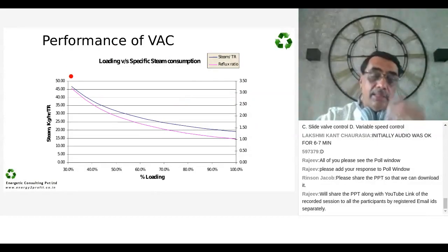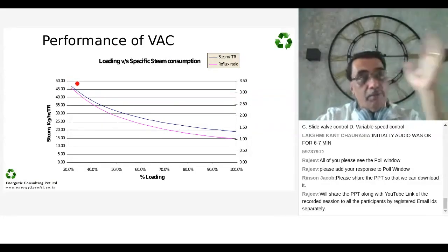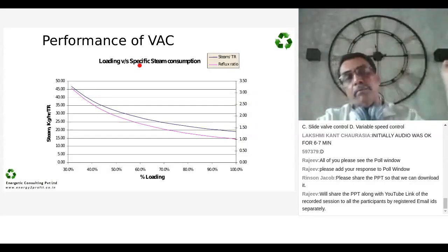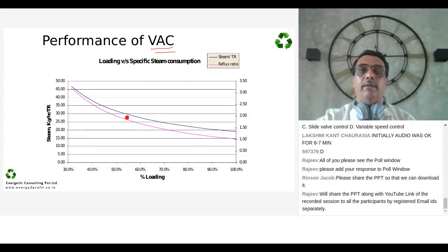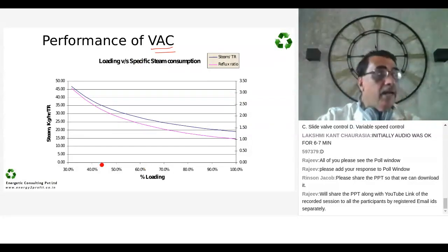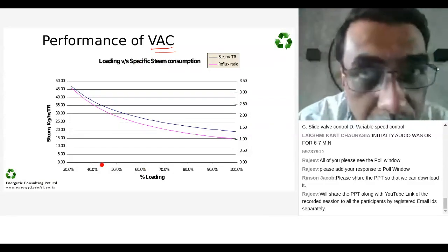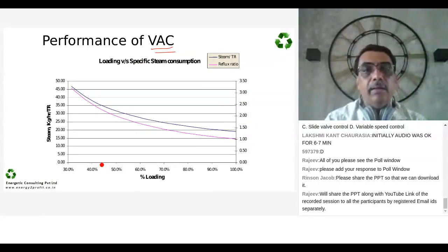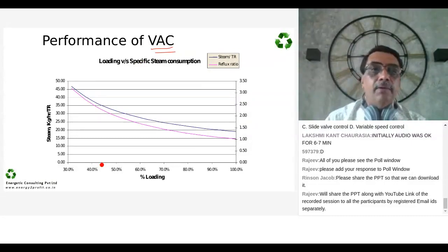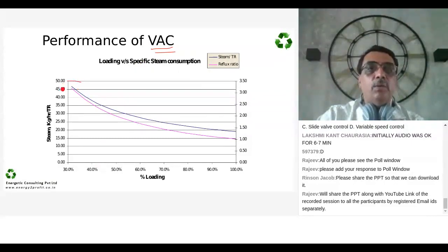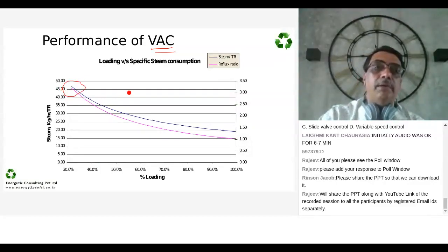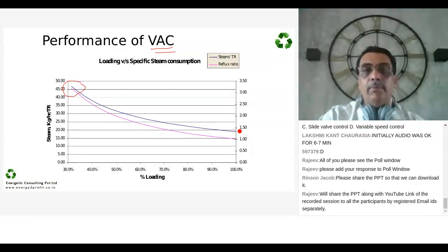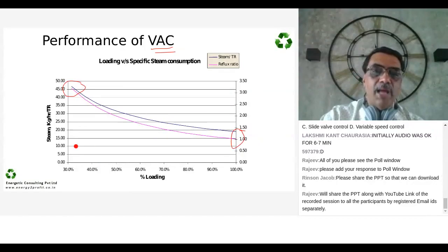This is like we saw part load performance of a vapor compression system. For vapor absorption, you have a similar one. This was again a trial done by us on a live system, with minus 20 degree brine and steam as the medium. So the steam consumption goes as high as 45 kg per TR from the lowest of 8 kg per TR as the percentage loading goes low.